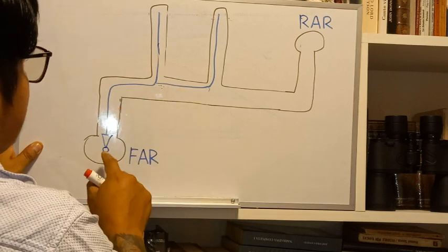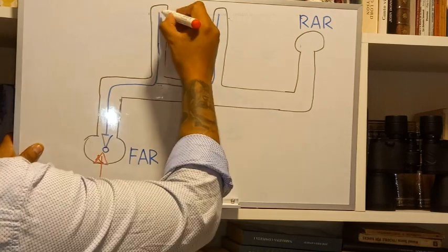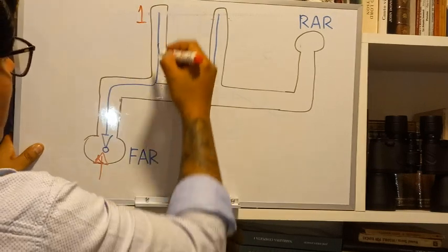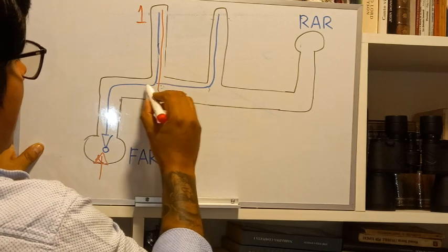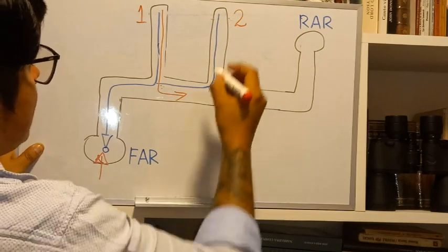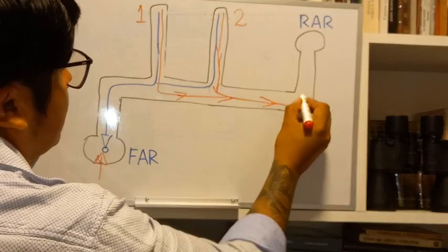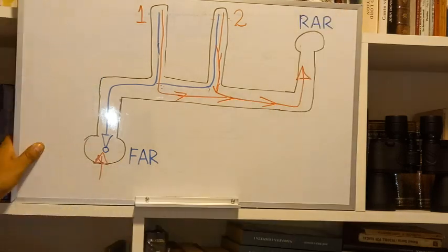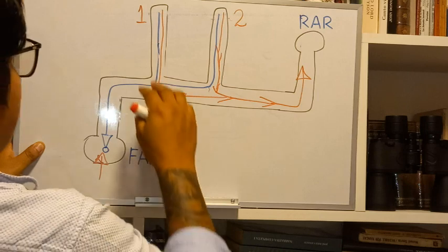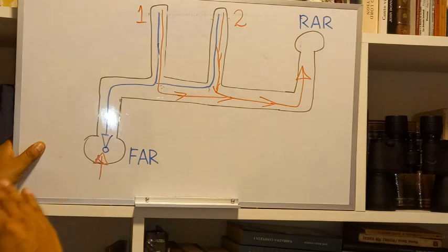Okay, so this is a parallel system. We have just one fresh air source here, and the contaminated air from this working phase number one is going to do this, and the contaminated air from this working phase number two is going to do this, and these two are going to go to the return air race. In this way, we are making sure that people here are going to receive fresh air, not contaminated air.